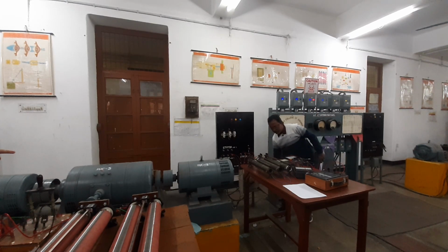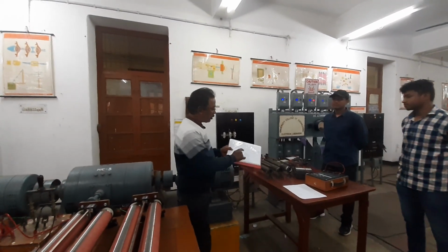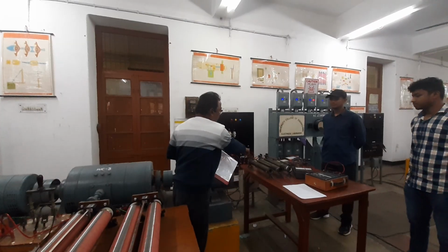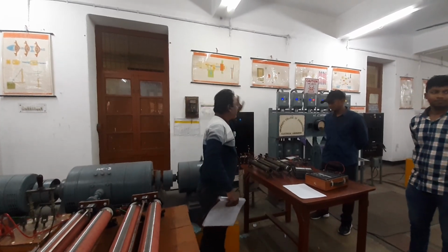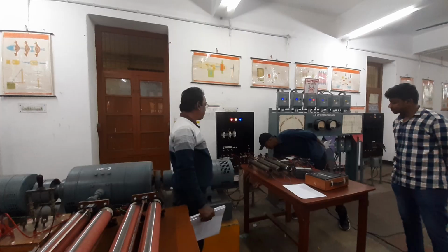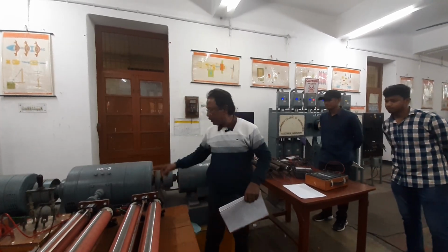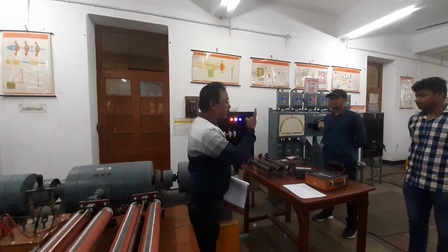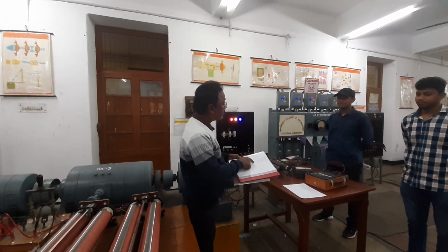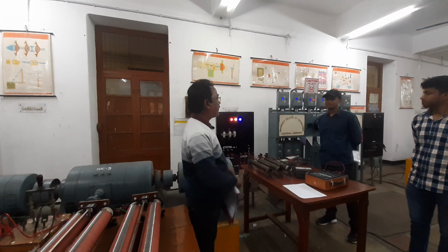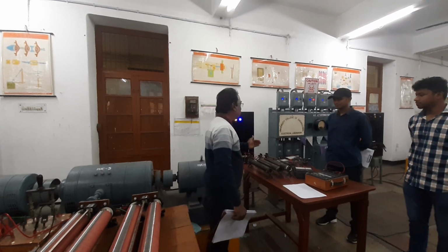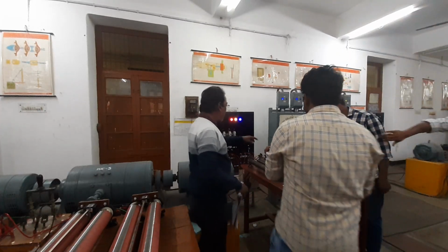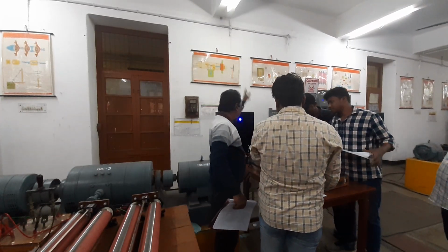Let us start the induction part. So this resistance should be at 100% as already discussed. This is at the 100% position, and make it start. The motor is started, it is rotating. So what you have to do? You have to make that one an induction motor, three-phase induction, not generator, motor. So for that purpose, you gradually, in a balanced way, increase the resistances. You come forward one by one. Don't keep it short circuited, otherwise a heavy fault will occur.